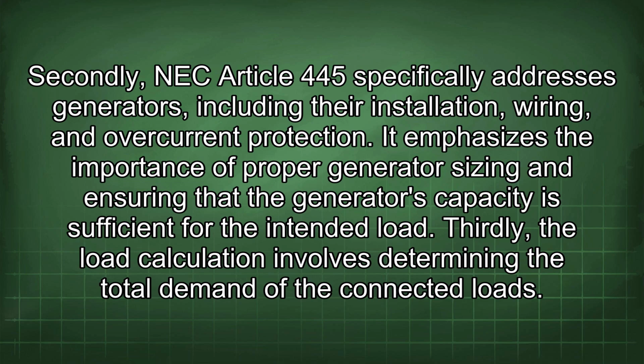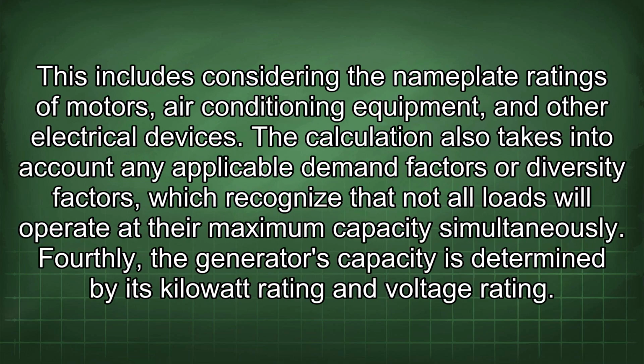Thirdly, the load calculation involves determining the total demand of the connected loads. This includes considering the nameplate ratings of motors, air conditioning equipment, and other electrical devices. The calculation also takes into account any applicable demand factors or diversity factors, which recognize that not all loads will operate at their maximum capacity simultaneously.